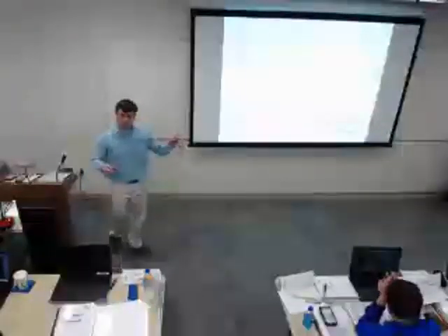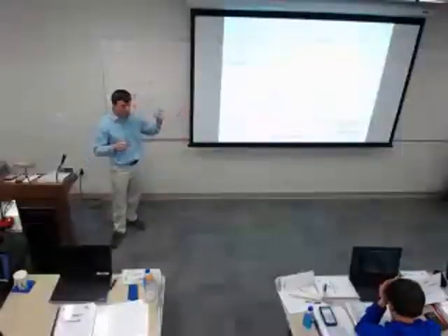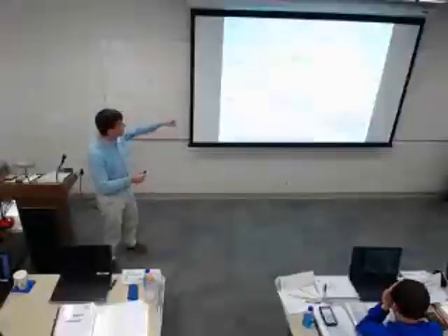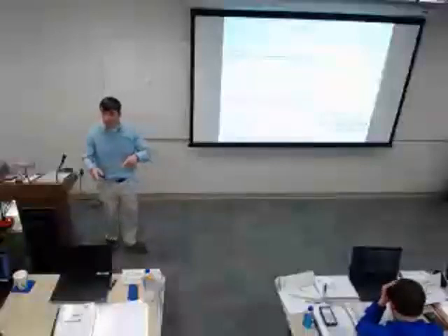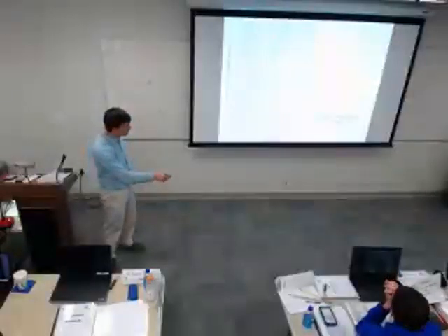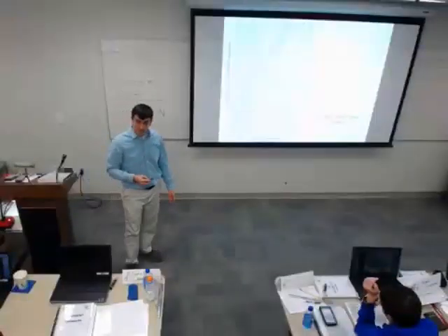That's correct. You go back and look at your chart. I don't think you might do this in the lab. I think you go through a system effects part of the lab, but you would need to go find whatever the chart is, like I've got them here for inlet elbows, and evaluate that for your situation if it matters. And you might find that, yes, it's not just the effective duct length, it's also velocity. And if I land on an X until I get to 4,000 feet per minute, it still doesn't matter. Or at least it's not 0.1.